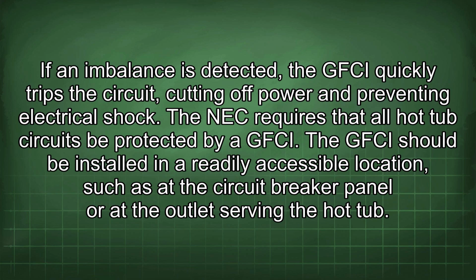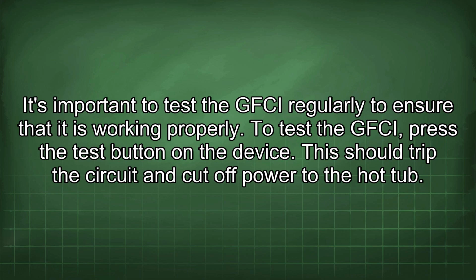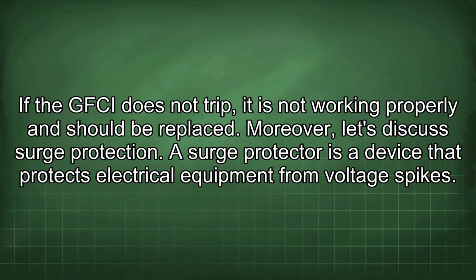The GFCI should be installed in a readily accessible location, such as at the circuit breaker panel or at the outlet serving the hot tub. It's important to test the GFCI regularly to ensure that it is working properly. To test the GFCI, press the test button on the device. This should trip the circuit and cut off power to the hot tub. If the GFCI does not trip, it is not working properly and should be replaced.